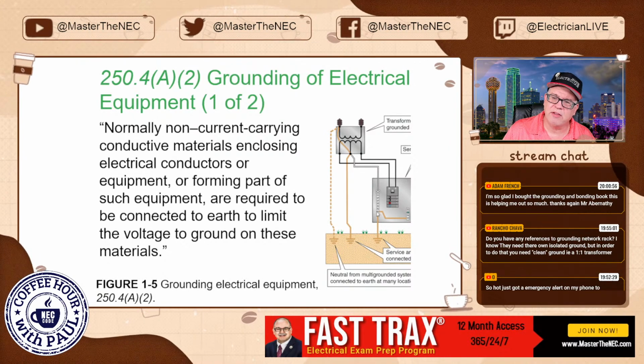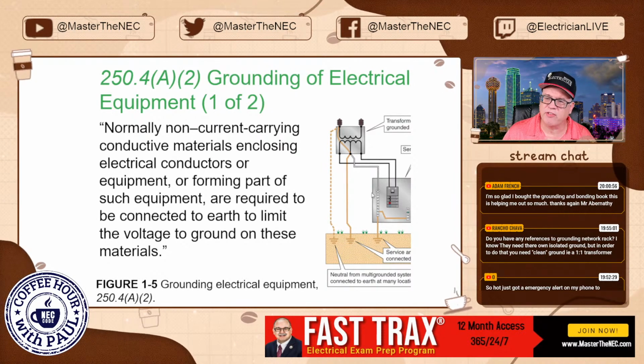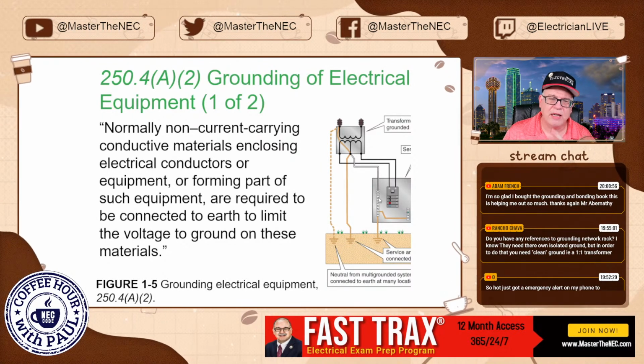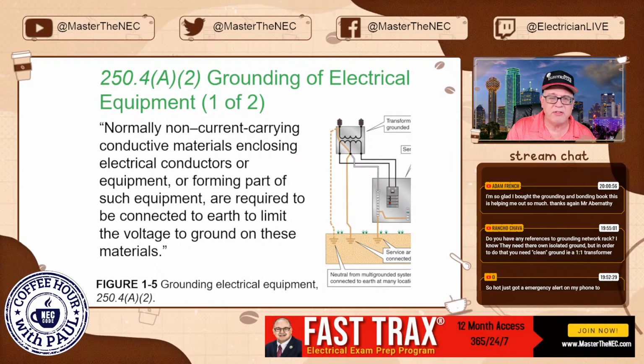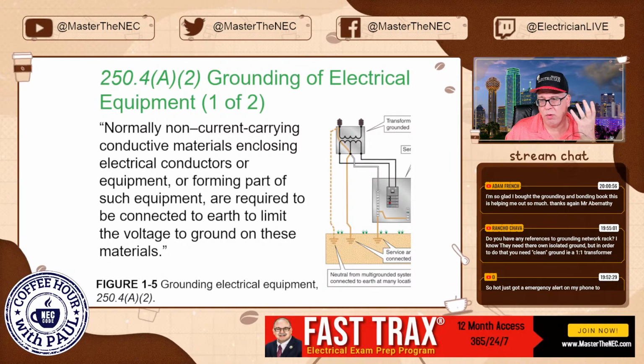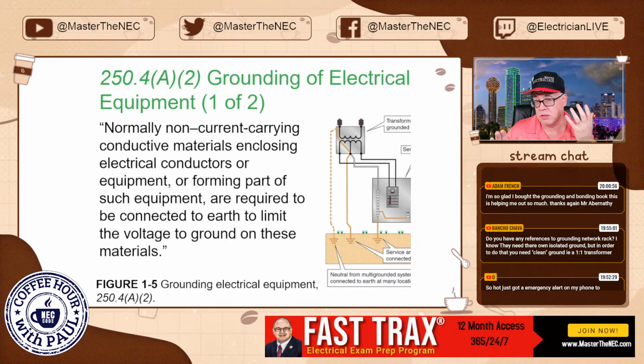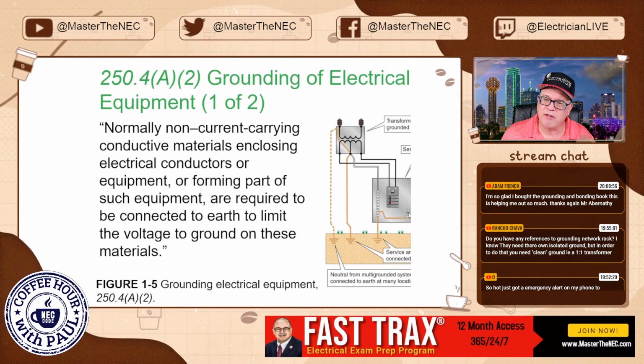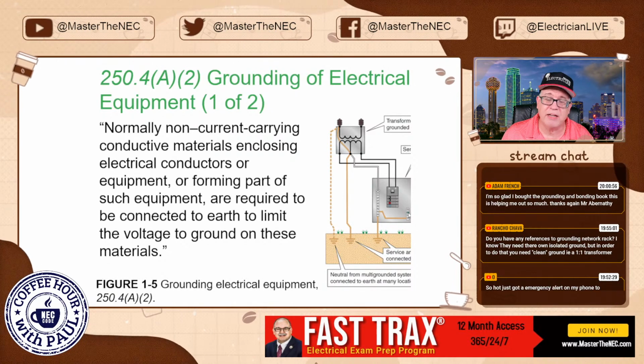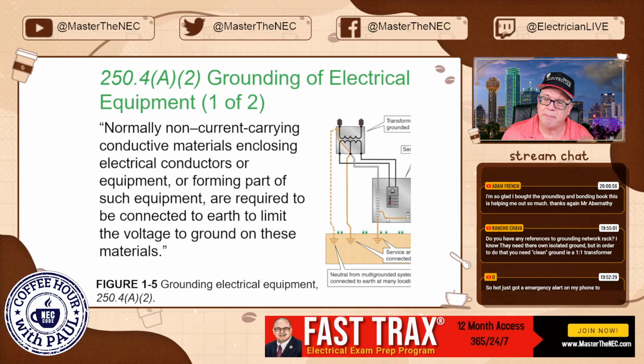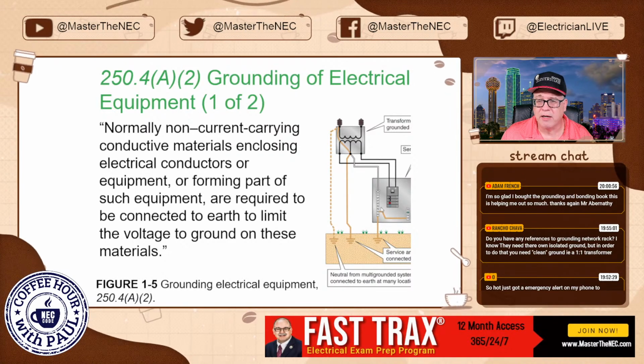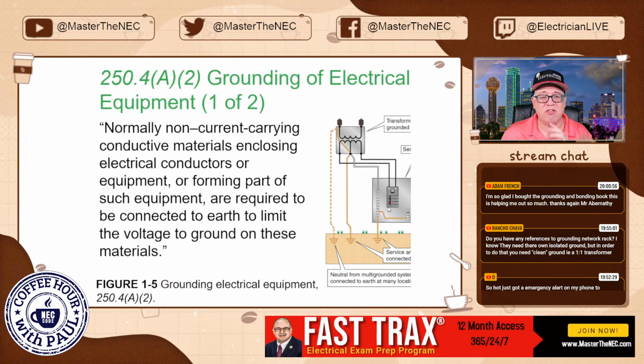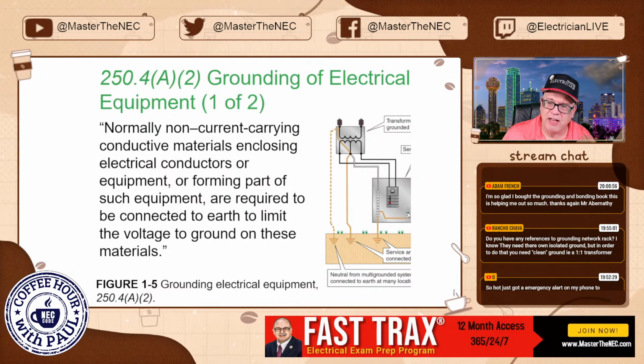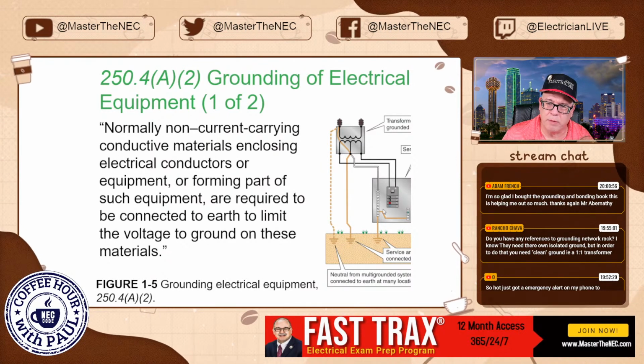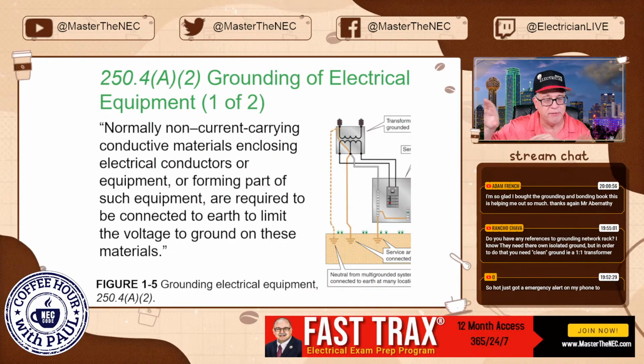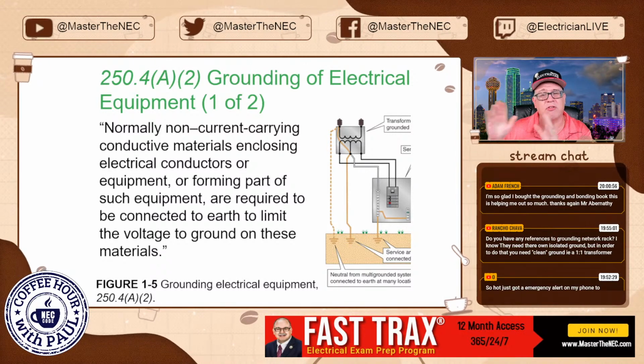Now, a lot of times, this can all be depicted on one bus bar. You could have just had this one bus bar and put this green screw on it. But Phil, who does these graphics, likes to separate stuff when we show it, because it can be used for many different explanations. So he separates it. So this green screw right here is not being used as the main bonding jumper. It's a bonding jumper, but this is the main bonding jumper because this is connecting the grounded conductor to the equipment grounds at the service equipment. So just don't be fooled by this. This green screw could be over here and it could be just one bus. Okay, we're not talking about a remote distribution panel here, folks. A sub-panel. We're talking about the service equipment right here.